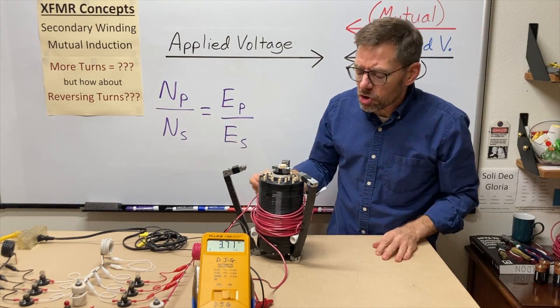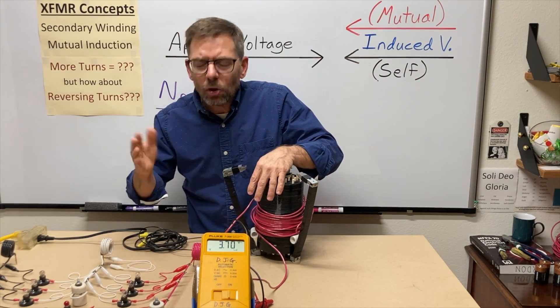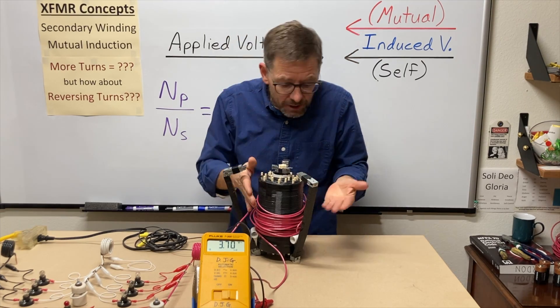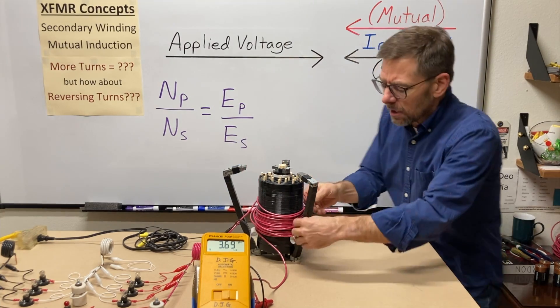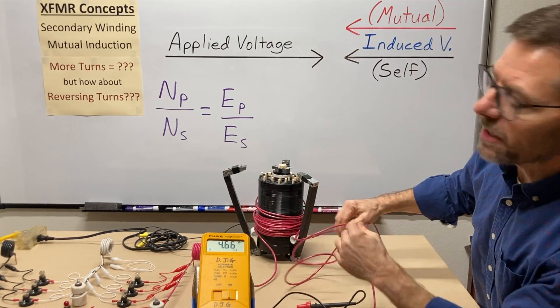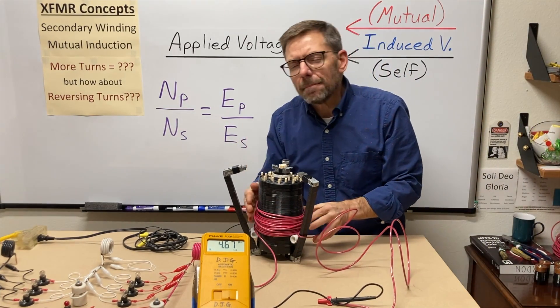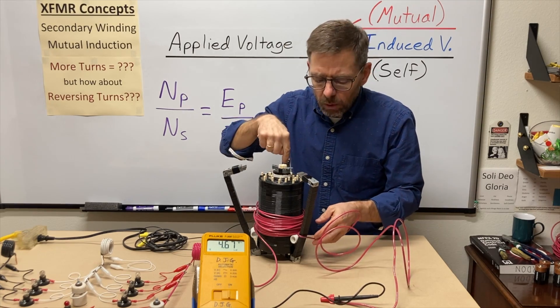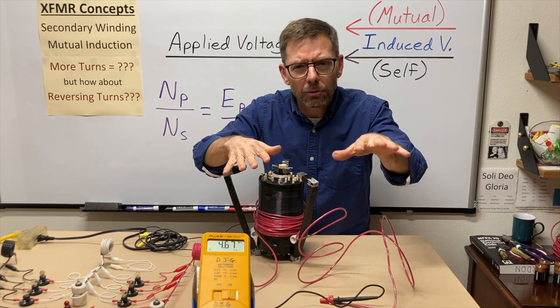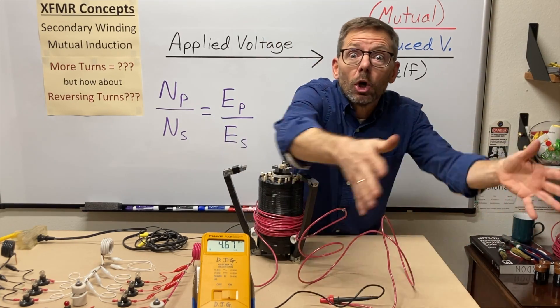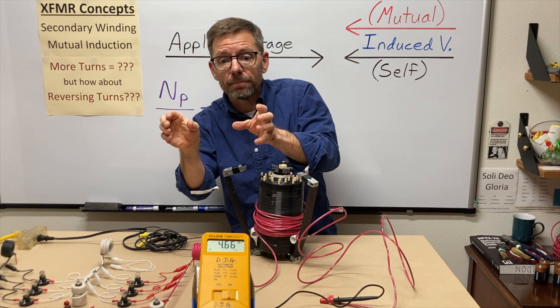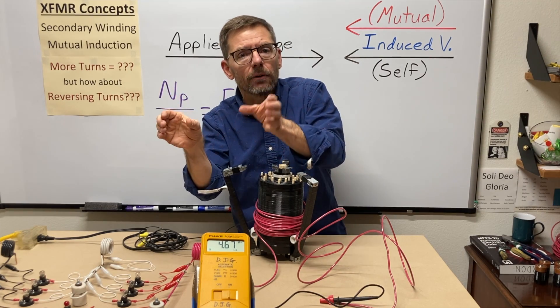It's a phase relationship concept. I have another video — I call it '120/240 volt in phase or out of phase' — where I explain what happens when you reverse the windings. As long as the whole secondary is wound the same direction, it doesn't matter whether it's clockwise or counterclockwise — it just affects the secondary sine wave relative to the primary. Where it matters is with buck-boost transformers or when paralleling transformers together, where you need the sine waves synced up.